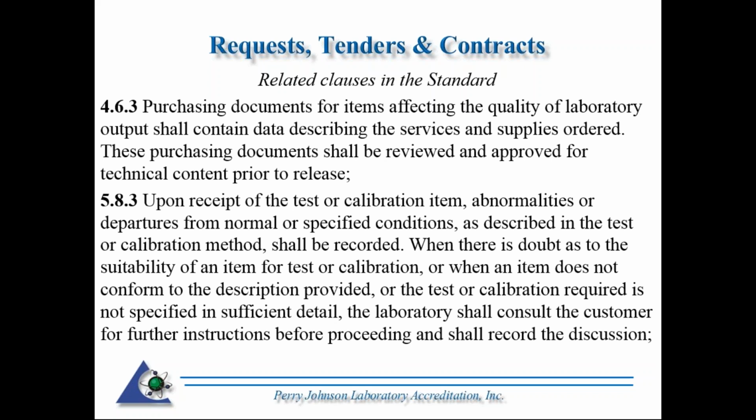When there is doubt as to the suitability of an item for test or calibration, or when an item does not conform to the description provided, or the test or calibration required is not specified in sufficient detail, the laboratory shall consult the customer for further instructions before proceeding and shall record the discussion. Hence, that last sentence I read in regards to not being provided sufficient detail sort of goes hand in hand with what we just read in section 4.6.3.